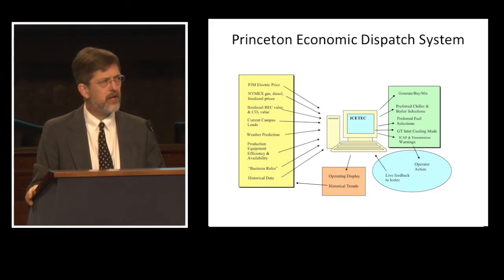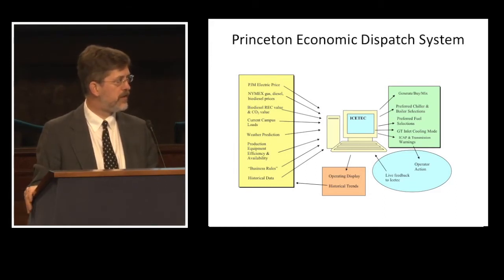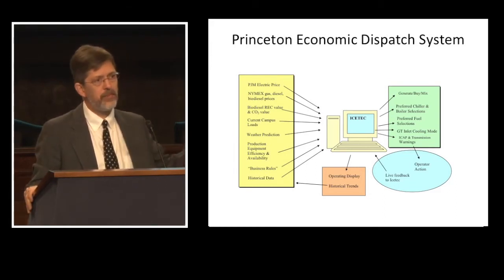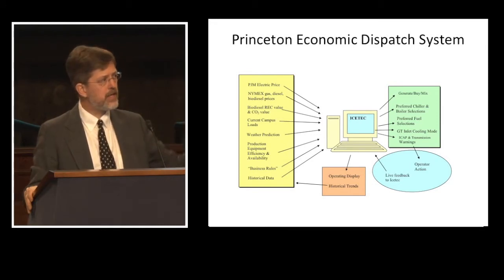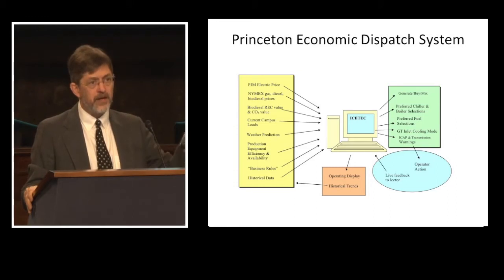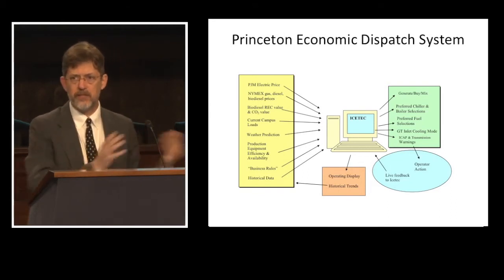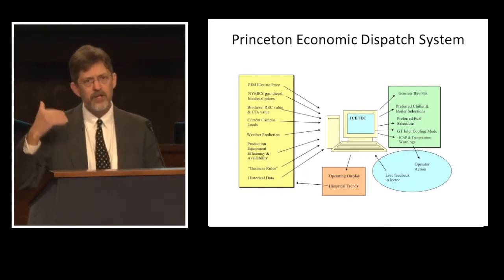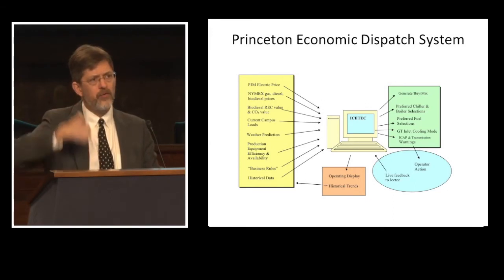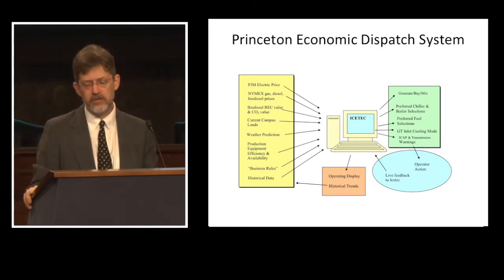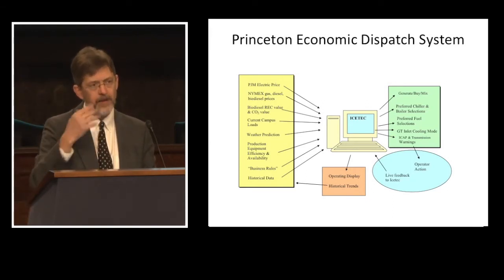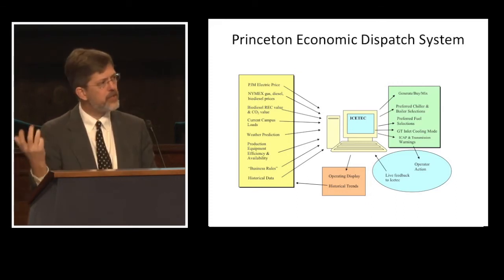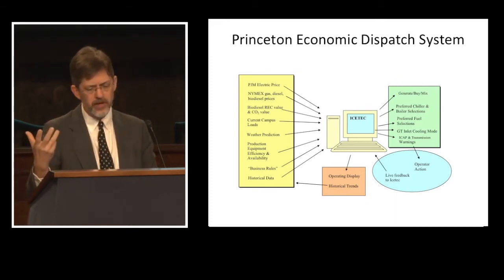We've also accumulated 13 years worth of historical data, so we can look back and say: under these weather conditions, at this temperature, at this humidity, on this day of the week, what energy demands did the university have? How much heating, how much cooling did we need under this circumstance in the past? We use that to inform our 24-hour forward prediction model that tells us what we should do, and then this system advises us whether to generate power, buy power, or do some kind of a mix.